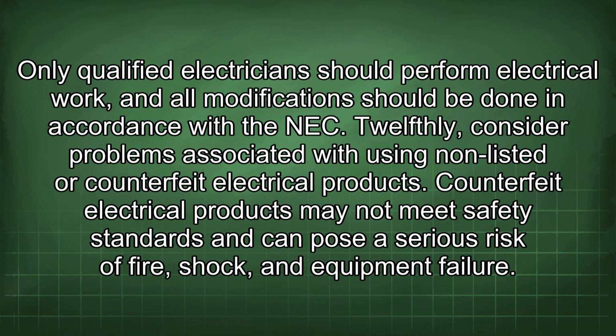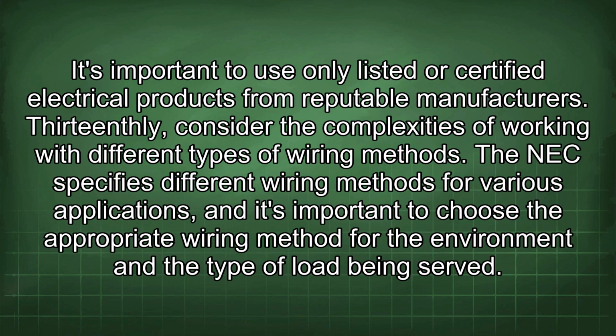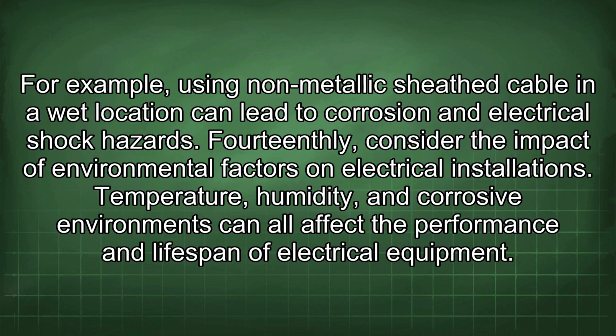12thly, consider problems associated with using non-listed or counterfeit electrical products. Counterfeit electrical products may not meet safety standards and can pose a serious risk of fire, shock, and equipment failure. It's important to use only listed or certified electrical products from reputable manufacturers. 13thly, consider the complexities of working with different types of wiring methods. The NEC specifies different wiring methods for various applications, and it's important to choose the appropriate wiring method for the environment and the type of load being served. For example, using non-metallic sheathed cable in a wet location can lead to corrosion and electrical shock hazards.